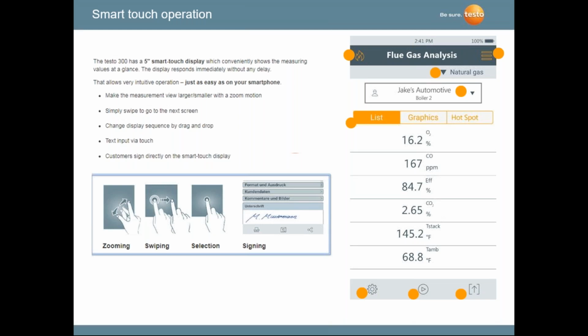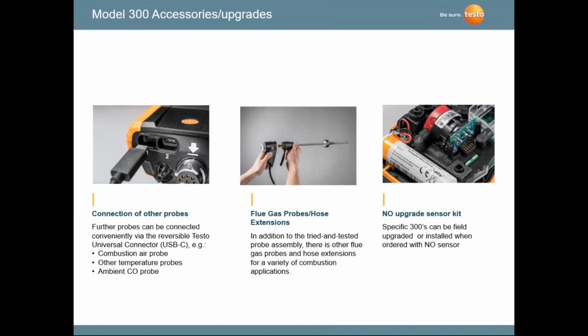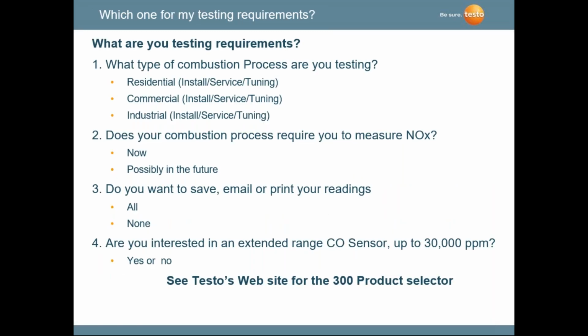And it's important that you select the right fuel so it calculates the combustion efficiency correctly. We went through the list, the graphics, the hotspot, the bottom 3 buttons. The center one is the on off for the pump. The up arrow key is for you to print, save, and email location to email to your customers and users and your supervisor. Again, we talked a little bit about this already. I'm not going to dwell on it, but these sensors are replaceable in the field.